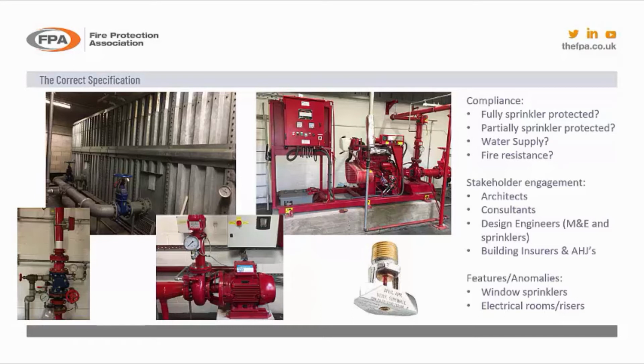So again, while space is an absolute premium and everything's trying to be shoehorned into the smallest possible space, if you've got these requirements, it's only going to increase the requirement for stored water capacity. Therefore, engagement with the local water authority may be required, so that we can test their water supplies to make sure that, within the period of time that's required for the system, if it was ordinary hazard, it's a 60-minute stored water, the water that's used from the town's main can make up the difference if you've had to reduce the size of the sprinkler tank. These are all things that need to be considered in the specification to ensure that it's correct from the word go.